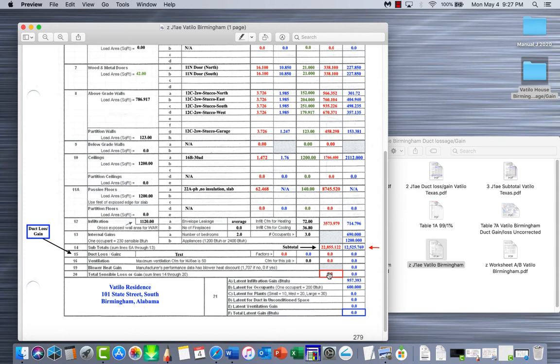Everything up here, when we finally get down to line 20, will be your sensible heating, sensible cooling, and then we'll have our latent load. Latent load deals with any type of moisture - this just deals with heating and cooling, raising temperature, dry bulb typically. Now we're ready to move on to our duct loss and duct gain.